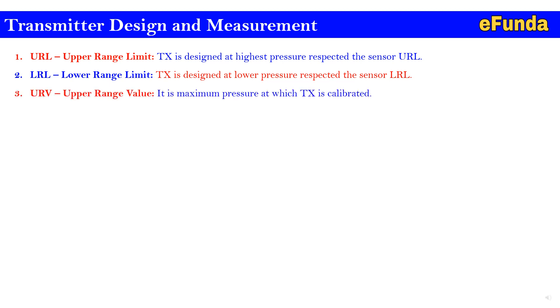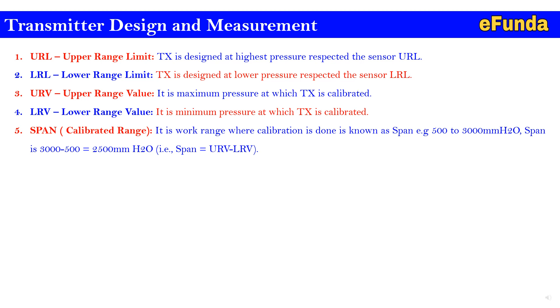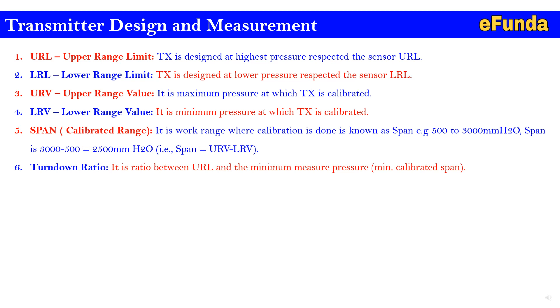URV is the Upper Range Value — the maximum pressure at which the transmitter is calibrated. LRV is the Lower Range Value — the minimum pressure at which the transmitter is calibrated. Span, also called calibrated range, is the working range where calibration is performed. For example, 500 to 3000 mm of H₂O gives a span of 2500 mm of H₂O. Span equals URV minus LRV.